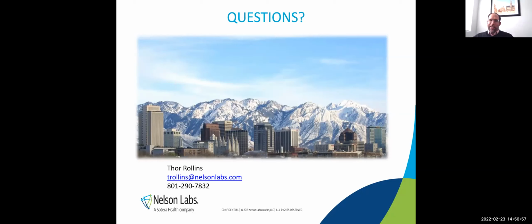Great question. I'm wondering if I might know the person who asked this. This is a draft guidance that came out in 2020. I love this. In fact, I did a webinar on this. It's called the Naughty and Nice list, if you want to look it up. The FDA lists a bunch of materials that they consider safe for skin contact. And then they list a bunch of materials they consider not necessarily unsafe, but that you have to evaluate for skin contact.